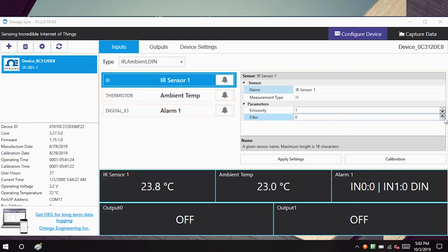Now let's open the emissivity dropdown and enter the known emissivity value for ice, which is 0.97. And click Apply Settings. And now we can see the temperature reading of the ice is 0, or pretty close to it. But what if you don't know the emissivity of the surface that you're calibrating to?